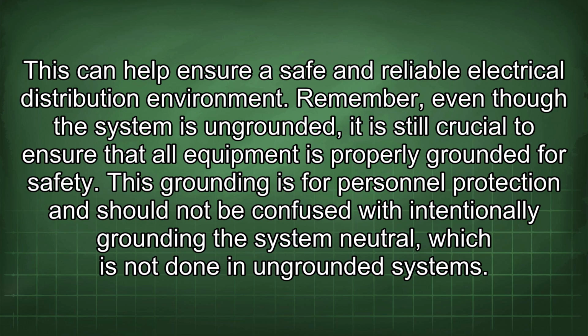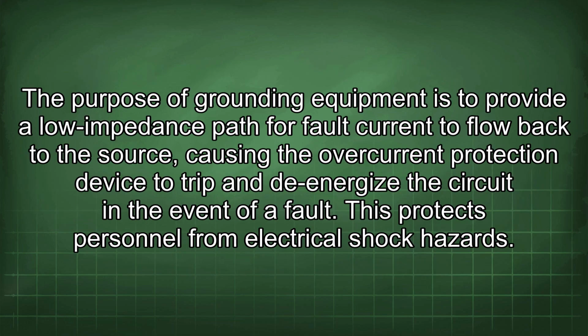Remember, even though the system is ungrounded, it is still crucial to ensure that all equipment is properly grounded for safety. This grounding is for personnel protection and should not be confused with intentionally grounding the system neutral, which is not done in ungrounded systems. The purpose of grounding equipment is to provide a low impedance path for fault current to flow back to the source, causing the overcurrent protection device to trip and de-energize the circuit in the event of a fault. This protects personnel from electrical shock hazards.